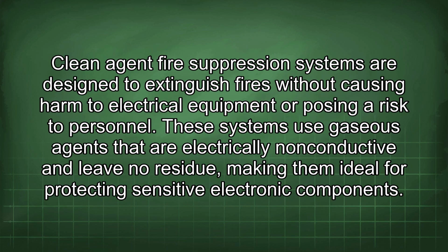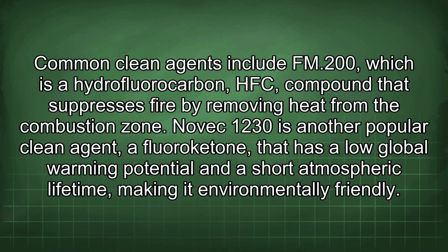Clean agent fire suppression systems are designed to extinguish fires without causing harm to electrical equipment or posing a risk to personnel. These systems use gaseous agents that are electrically non-conductive and leave no residue, making them ideal for protecting sensitive electronic components. Common clean agents include FM200, which is a hydrofluorocarbon (HFC) compound that suppresses fire by removing heat from the combustion zone. Novec 1230 is another popular clean agent, a fluoroketone that has a low global warming potential and a short atmospheric lifetime, making it environmentally friendly.